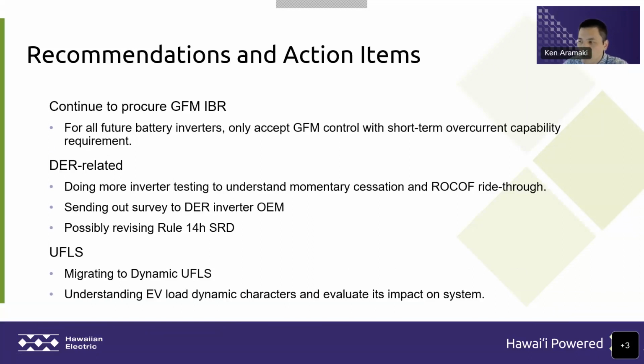So we are migrating to a dynamic UFLS system, and I did see a question about that, so I'll attempt to address that now. UFLS is currently a static system that just triggers at certain frequency drops, dropping certain feeders or distribution circuits. But a dynamic one takes actual measurements from the field, maybe every 15 minutes or so, to know what the net load on that circuit is, to determine which circuits are actually dropped in the event of an under-frequency event.